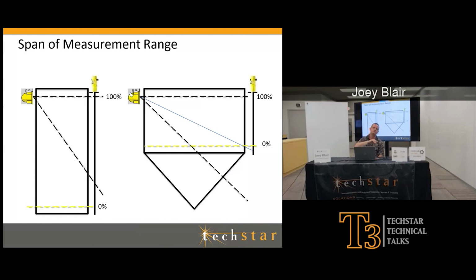So your first example, this is usually where I ask a question and wait for an answer, but we're not going to do that right now. But usually I'll say, well, I measure all the way to 0 here. Answer is, I'm probably not going to be able to read a very good 0 there. I might have a little bit of radiation leakage on the other side, or I get a little below it, but my resolutions can be horrible. And if I was out doing a calibration in the first picture there, I would tell you we either need to drop our 100% and lower our source holder a little bit, or we would need to raise our 0. One of those two things would have to happen. Or a third option would be to add another source holder to the measurement so that we can get our full span, if you do require a full span and shrinking it's not a possibility.